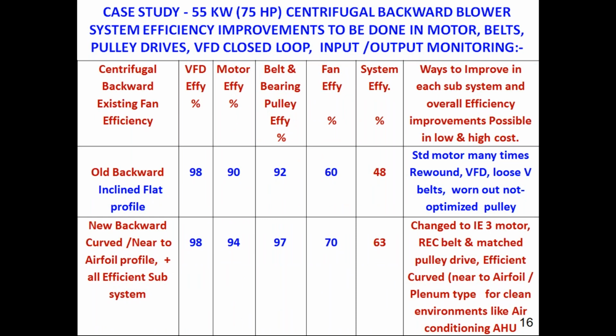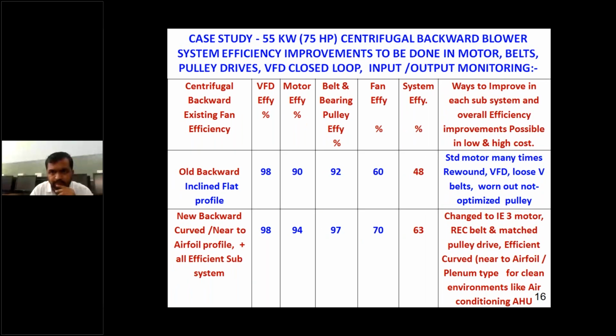I'm just starting with a blower, a typical 75 HP old blower, you can see in the first column. The old blower is operating with a poor, inefficient impeller. The motor efficiency and the belts and pulleys have a loss of around 5 to 10%, and the fan efficiency is only 60%. Ultimately, the multiplication of the efficiencies gives an overall system efficiency of less than 50% only. The OEMs claim it's around 70 to 80%, but that is not happening here.